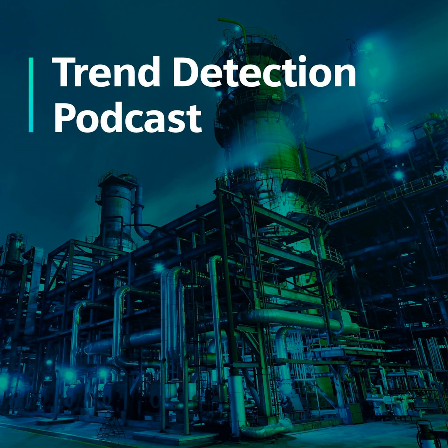Looking at predictive maintenance then, where we're looking to say when things are getting worse and you should intervene soon, you're taking away some of that guesswork. So you're now saying, well, instead of just going in at periodic points, actually, this asset's absolutely fine. The metrics are all saying it's running cleanly, and we're confident we'll get to the next maintenance window. Then you actually reduce the amount of parts you use, the amount of ancillaries, man hours that could be used elsewhere.